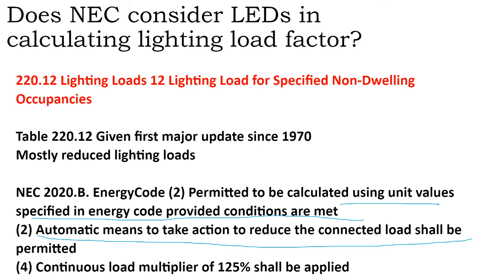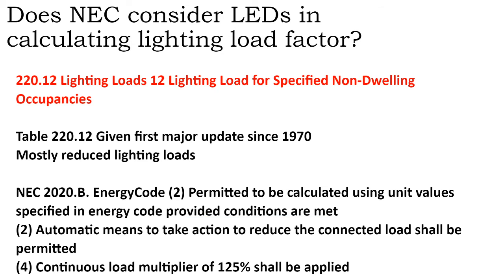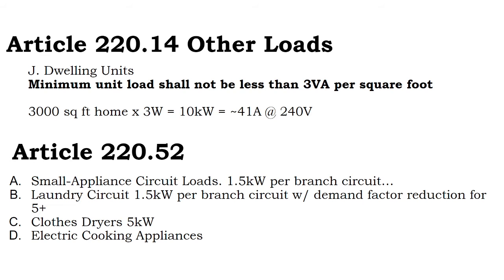And so whether it's solar or batteries or just digital load controls, which we talked about in a PDH Pro class last week, that's now available on demand, taking proactive measures to manage your building energy load might be able to help you if you're doing a large building with a very small power supply, because that's all the utility can provide you to be compliant with code. If you have a larger load on site than what the utility is capable of supplying, implementing some load management on site can get you out of that requirement.